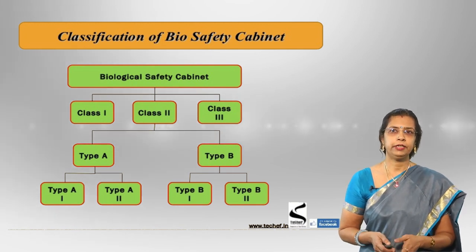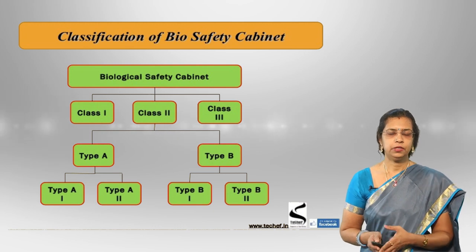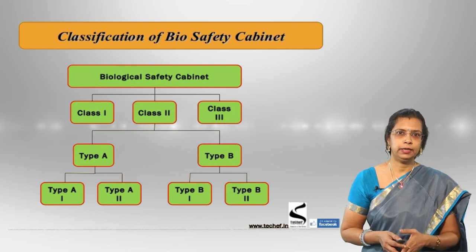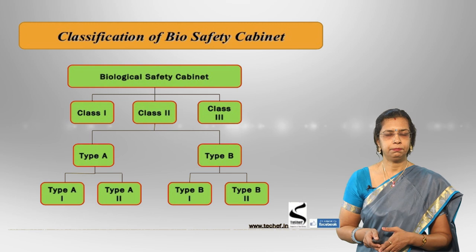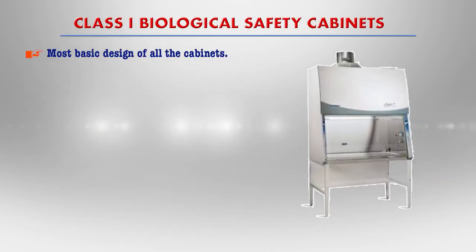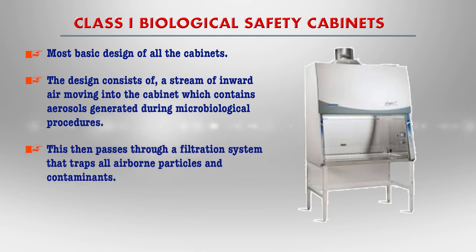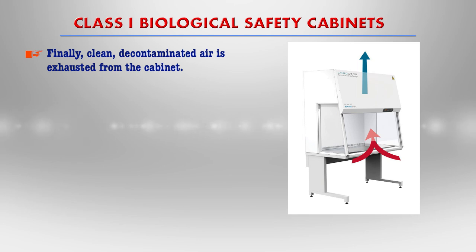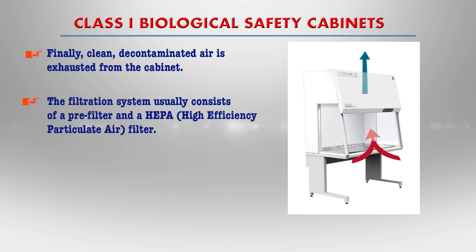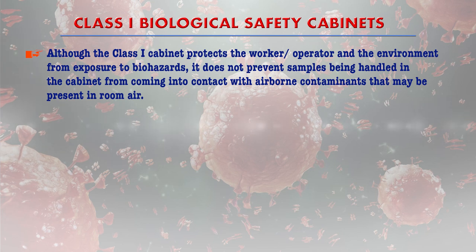In the classification, class 2 has type A and type B; type A has A1 and A2, and type B has B1 and B2. Class 1 biological safety cabinets are found in most laboratories and represent the most basic design. They consist of a stream of inward air moving into the cabinet, containing aerosols generated during microbiological procedures. This air passes through a filtration system that traps all airborne particles and contaminants, and clean decontaminated air is exhausted from the cabinet. The filtration system consists of a pre-filter and a HEPA — High Efficiency Particulate Air — filter.